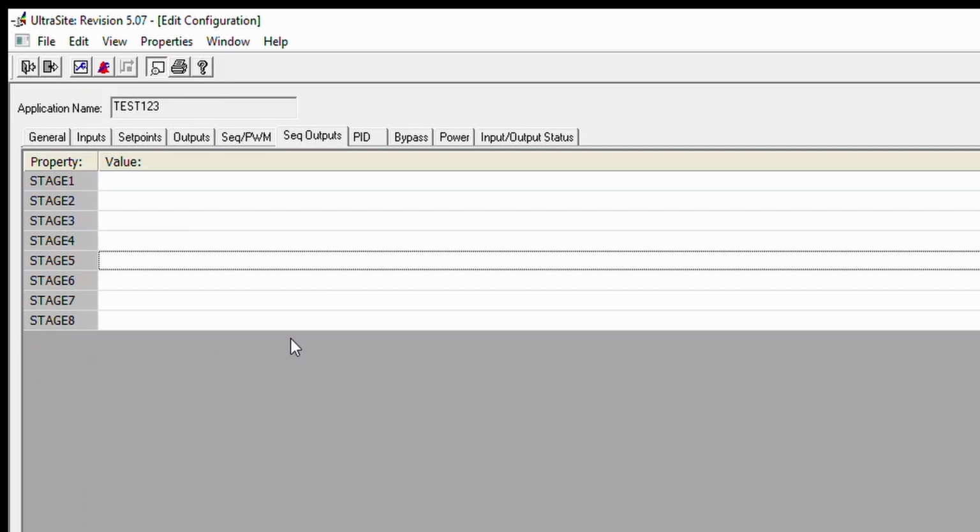Say if you wanted to stage up a rack like after a power outage, and you were killing the solenoids or the circuit enables, you had these tied to the clean switches, and as soon as the rack comes on, you let everything kind of pump down, and that way you don't slam a rack on right away. Great application for that. It's about the only application I use the PWM setup. It's a lot easier than writing a flexible combiner that somebody's going to have to look at. The PWM's a lot easier to troubleshoot.